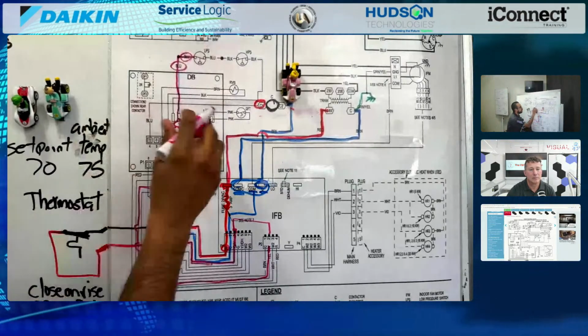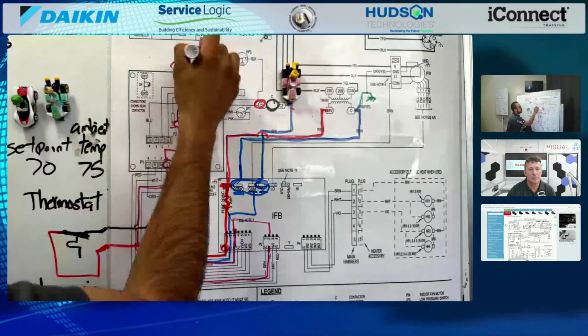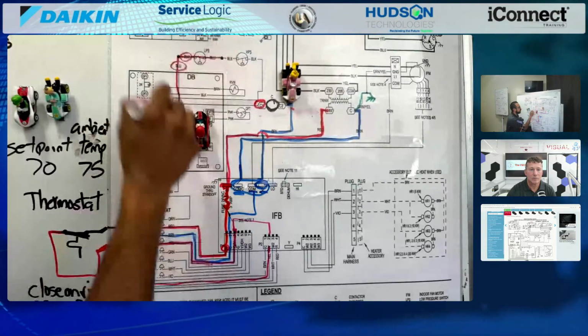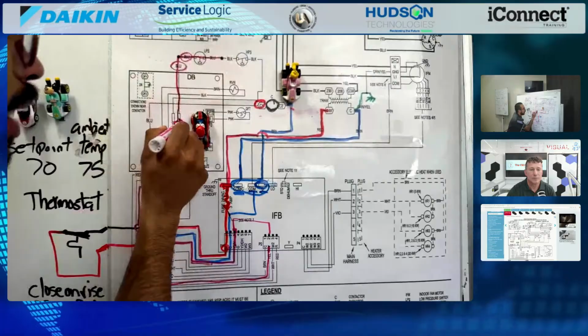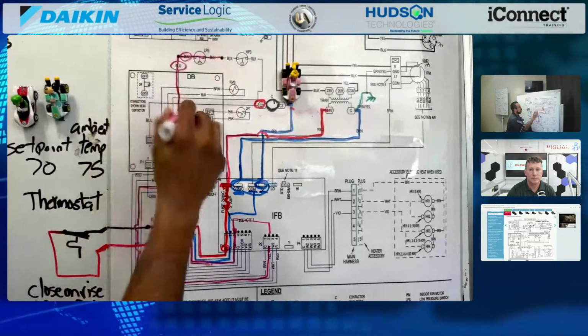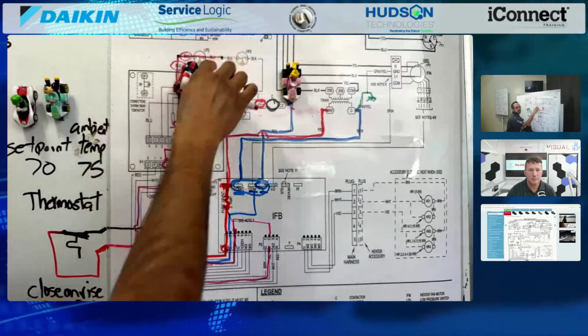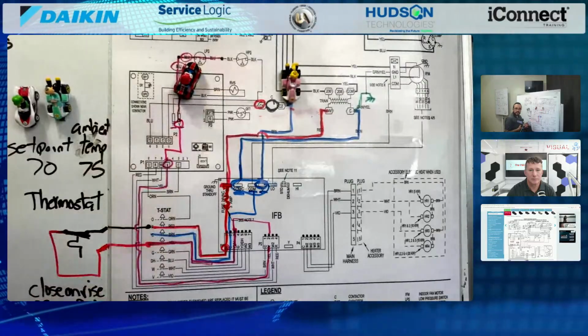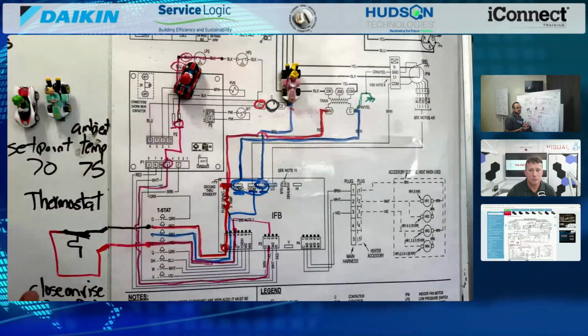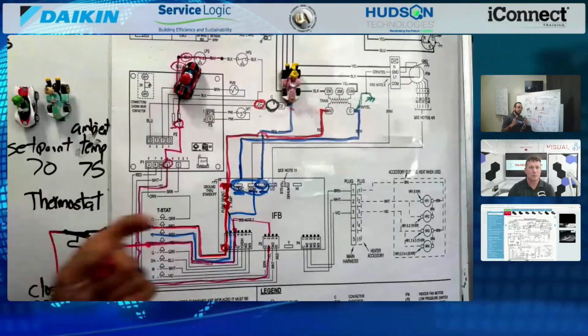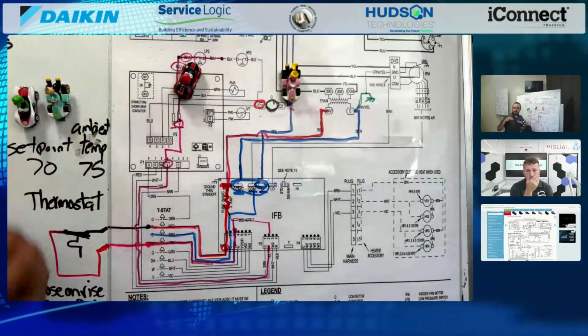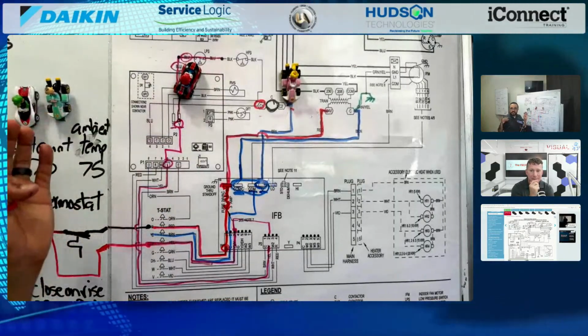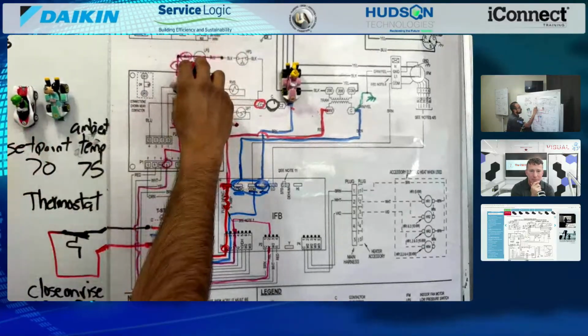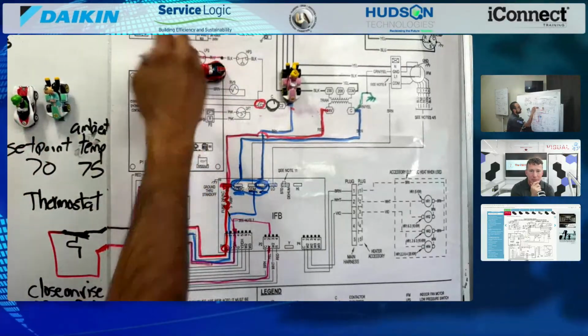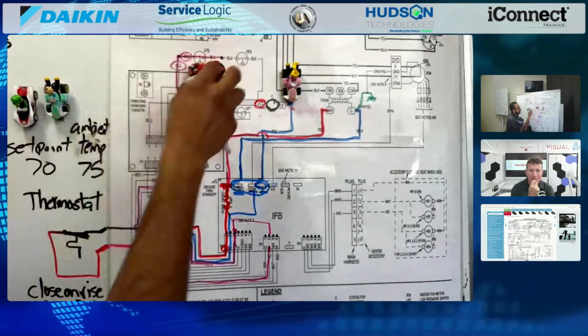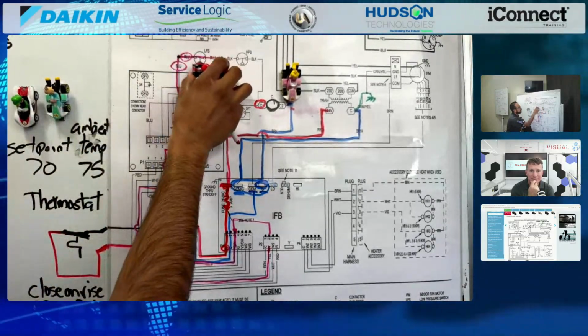So Mario continues, and it goes through my low pressure switch. It's a blue wire on Y coming out. And if that system isn't flat, it's properly charged with refrigerant, and I'm not saying pressure switches never go bad even when properly charged, that does happen. But if it's properly charged, Mario's going to go through because it's just a bridge, just closed. So boom, he made it through.